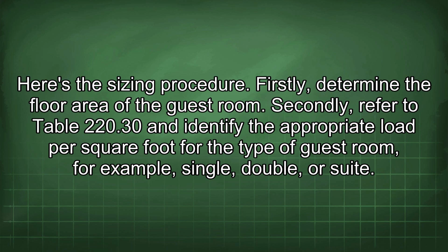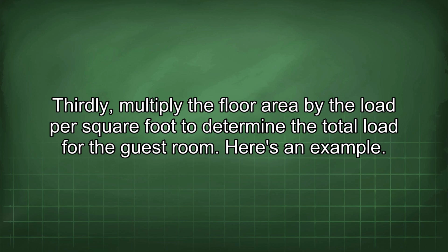Here's the sizing procedure. Firstly, determine the floor area of the guest room. Secondly, refer to Table 220.30 and identify the appropriate load per square foot for the type of guest room, for example, single, double, or suite. Thirdly, multiply the floor area by the load per square foot to determine the total load for the guest room.